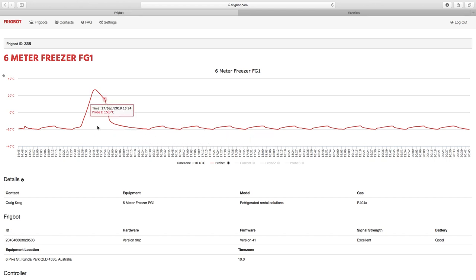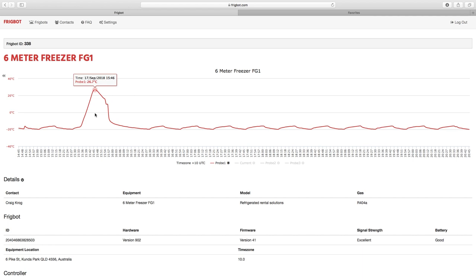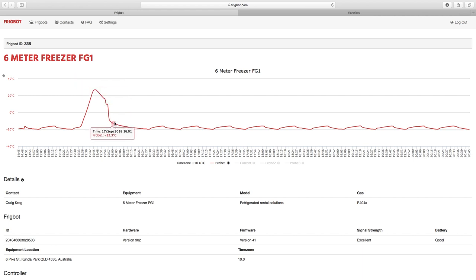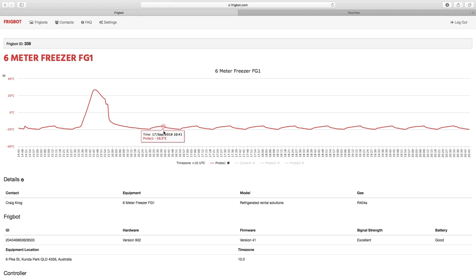This sudden peak in temperature over here indicates the machine has gone through a defrost, and straight after the defrost you can see the temperature is pulled straight back down until it's reached its target of minus 20 degrees.